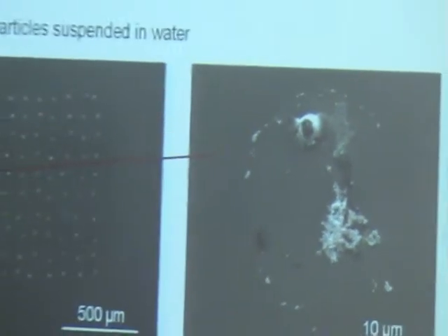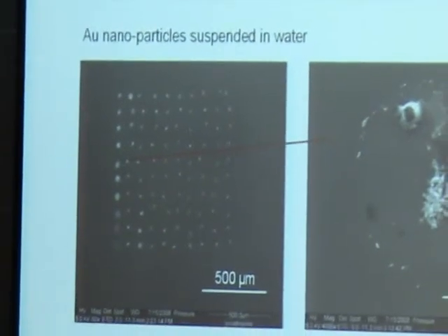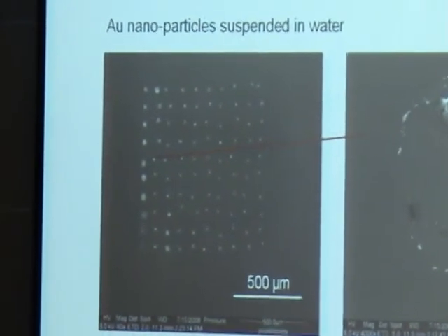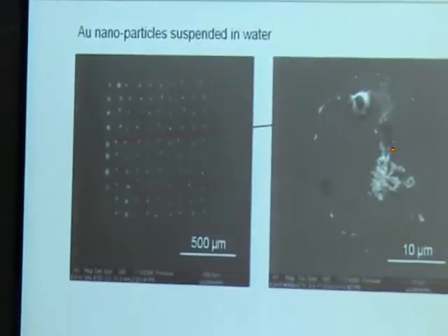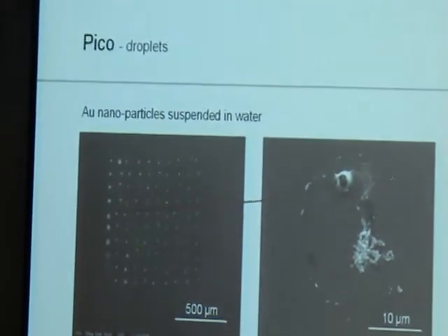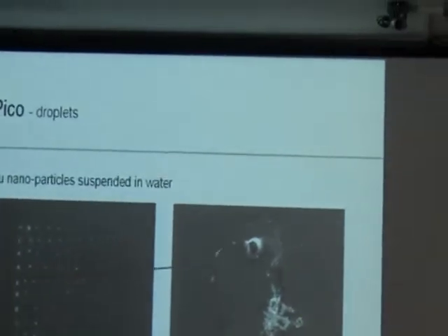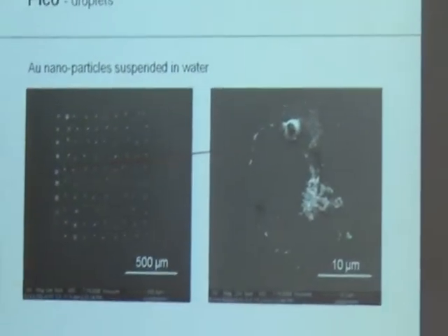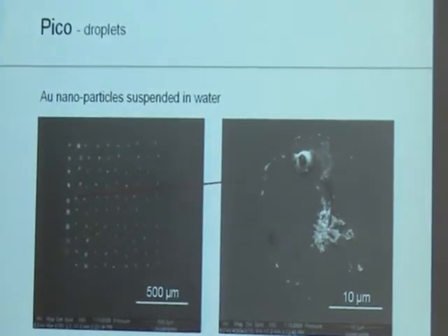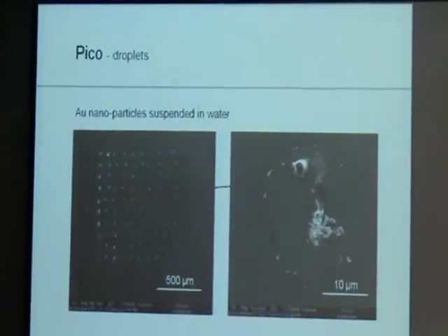The system, we store our sample. After ablation, we use very pure water. We stored it in a normal glass vessel with a plastic cap. And during 2 months, the glass was dissolved in the water. If you look at the elements distributed here, you will find calcium, boron, aluminum, silicon, potassium, elements present in the glass. So we have to take care where the particles are coming from before starting the analysis.